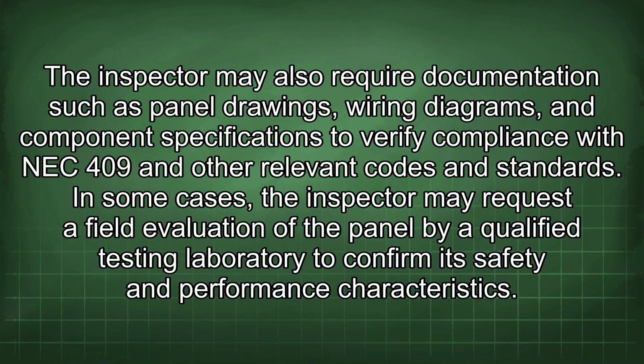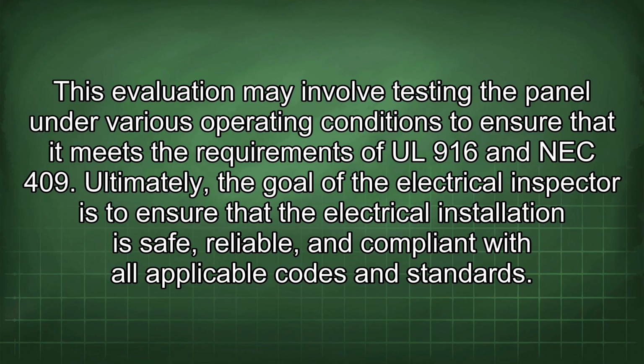In some cases, the inspector may request a field evaluation of the panel by a qualified testing laboratory to confirm its safety and performance characteristics. This evaluation may involve testing the panel under various operating conditions to ensure that it meets the requirements of UL 916 and NEC 409.